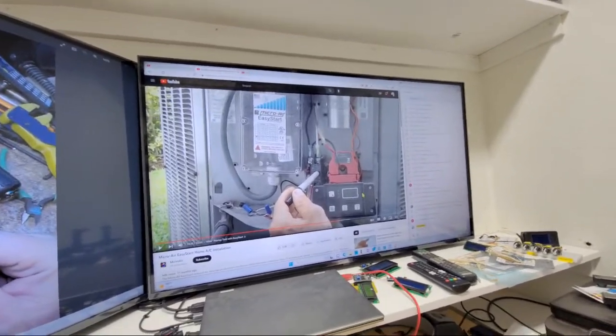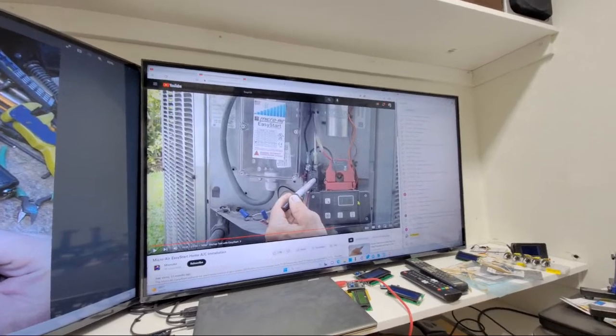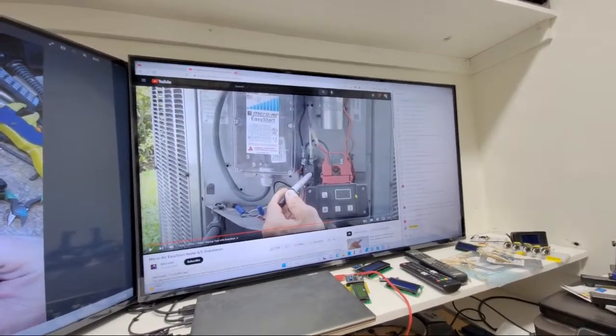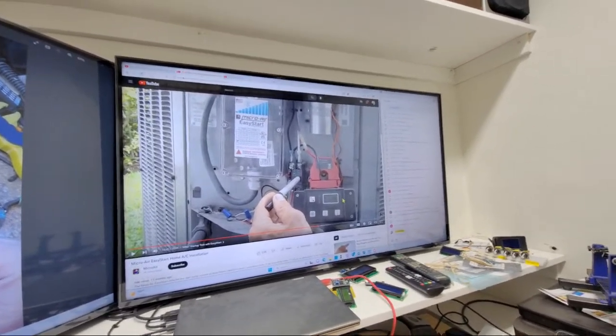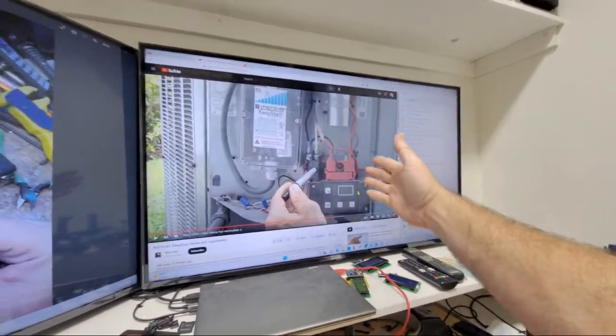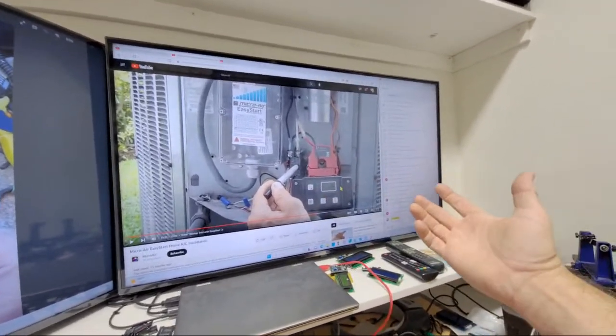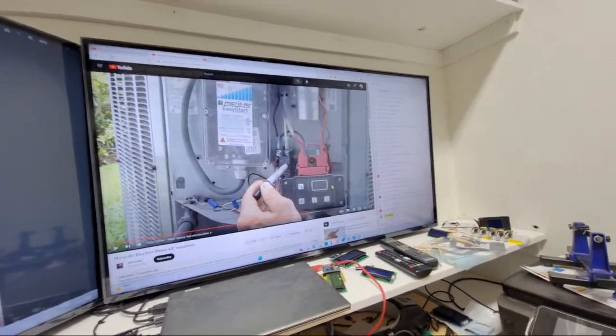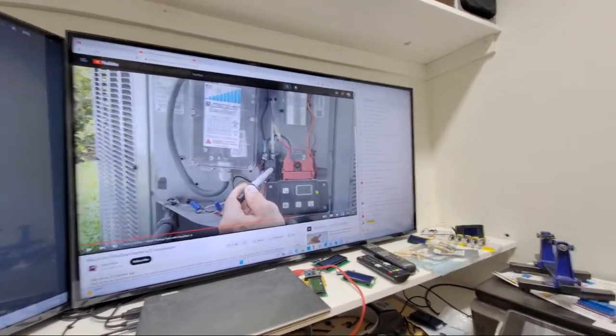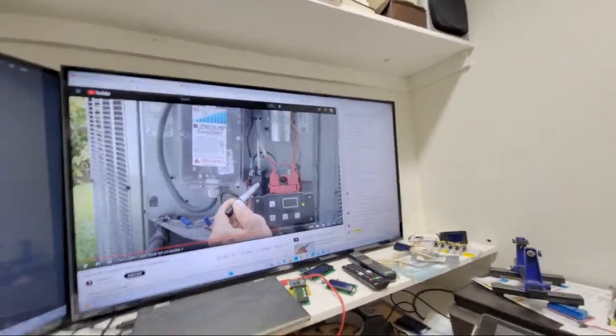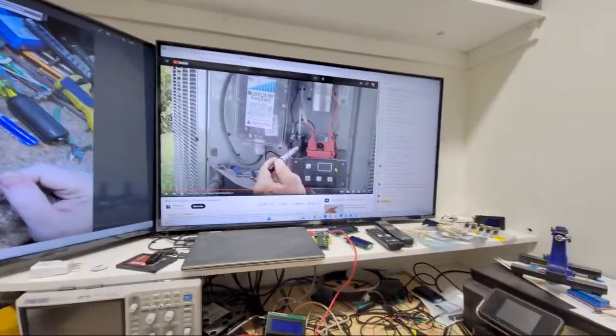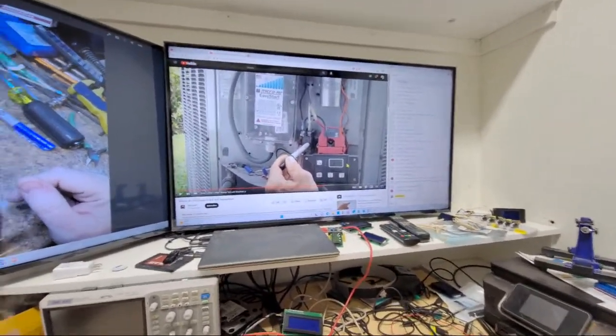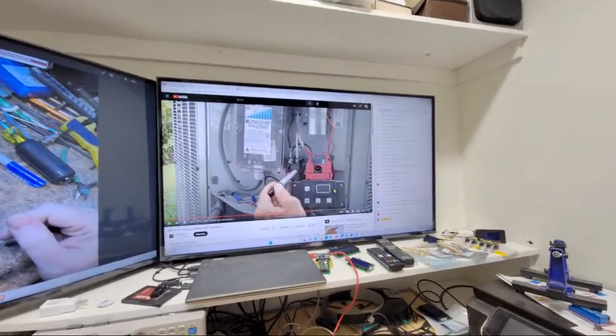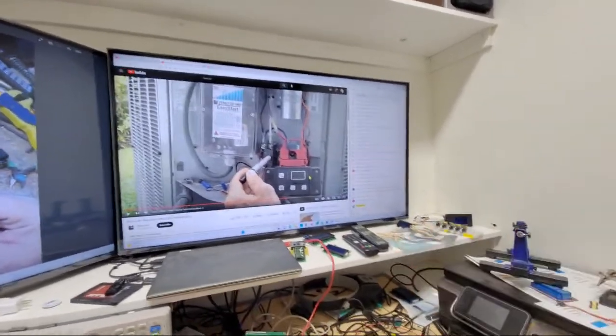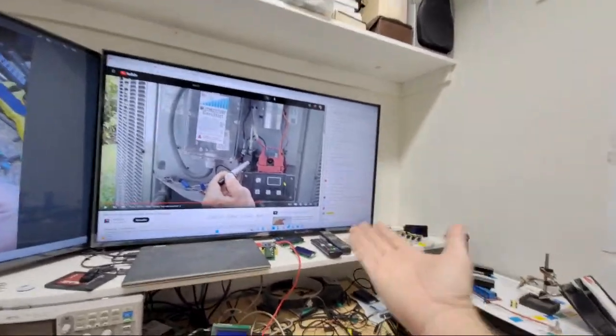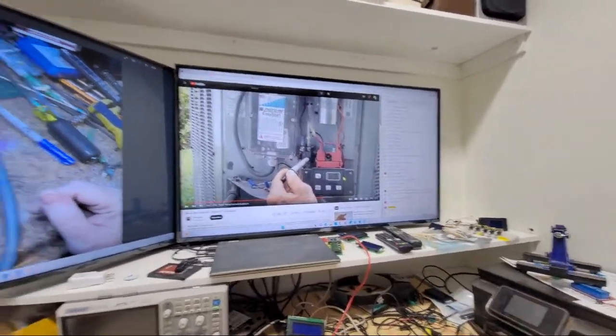Now here's the thing: when I've added a hard start, like a good one, I get the same kind of result. It's so much quicker that your sample time and measuring the peak current is way less. So the arbitrary value is comparable, it's just not reality. It still would have the same initial peak, with no rotation, no magnetic field, but it's just not going to capture it, because it's so much quicker the new value is like 20 instead of 70 something.